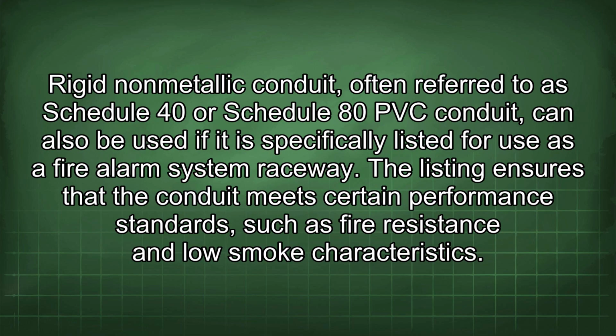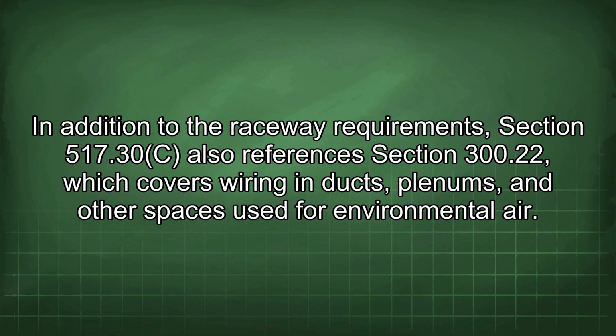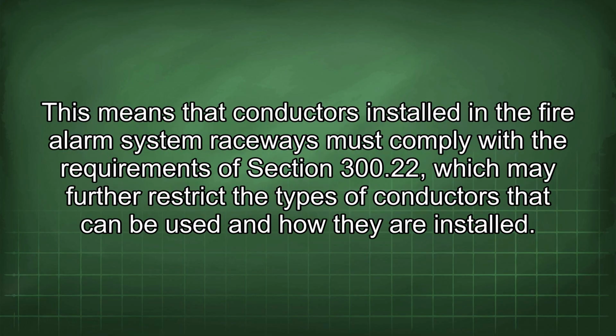Rigid non-metallic conduit, often referred to as Schedule 40 or Schedule 80 PVC conduit, can also be used if it is specifically listed for use as a fire alarm system raceway. The listing ensures that the conduit meets certain performance standards such as fire resistance and low smoke characteristics. In addition to the raceway requirements, Section 517.30c also references Section 300.22, which covers wiring in ducts, plenums, and other spaces used for environmental air. This means that conductors installed in the fire alarm system raceways must comply with the requirements of Section 300.22, which may further restrict the types of conductors that can be used and how they are installed.